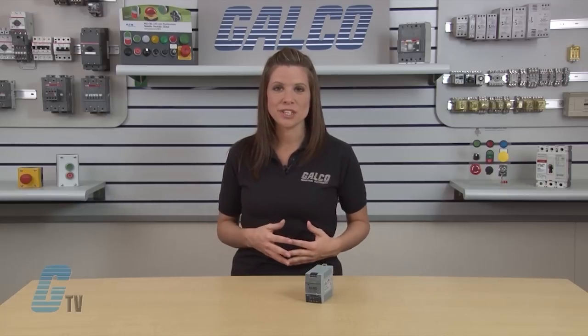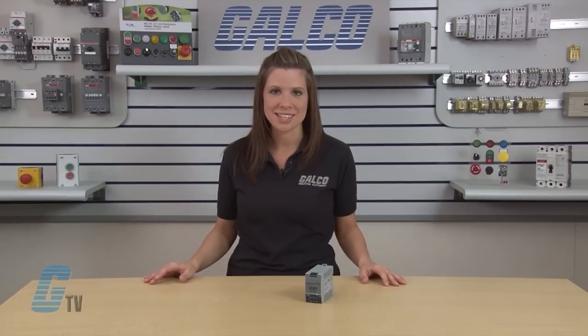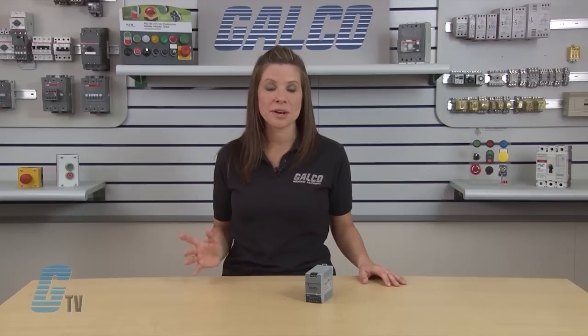Many extra industrial features are standard. The SDP's power boost overload circuitry can start up industrial loads such as motors, relays, solenoids, and DC-DC converters that can cause ordinary power supplies to fold back or shut down.